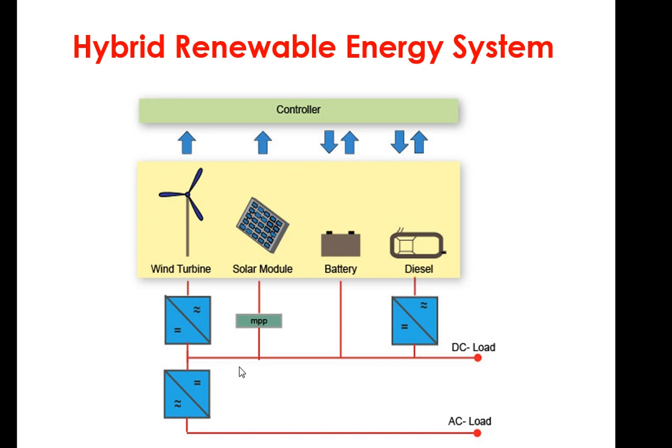In day-to-day life for modern hybrid systems, the DC bus is as high as 600 volt DC, because typical solar inverters, hybrid inverters or smart inverters can be operated above 550 or 600 volts, typically 600 volt DC. Sometimes it is 680 to 700 volt for grid tied wind applications. According to that, you will select the DC link voltages, which is inside the converter components, and you have already observed the waveform of the incorporation of the capacitors in power electronics.